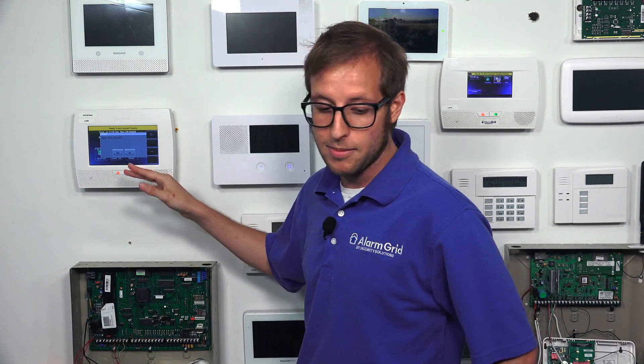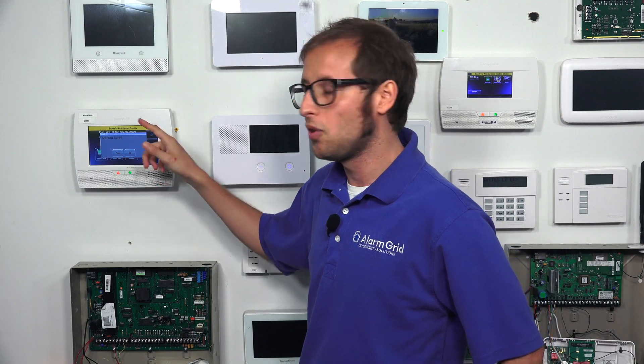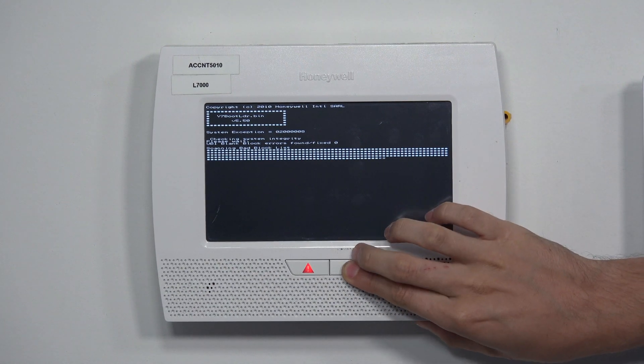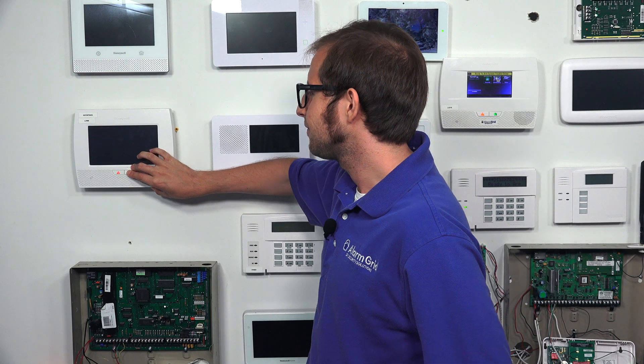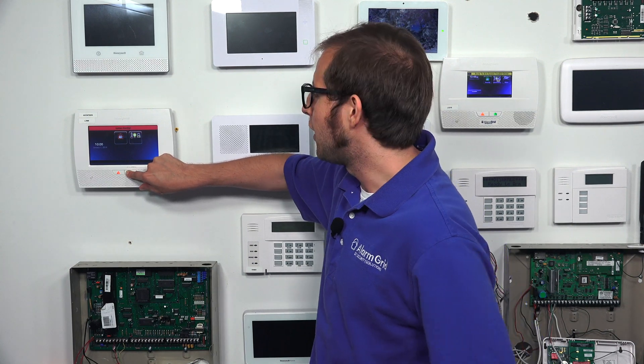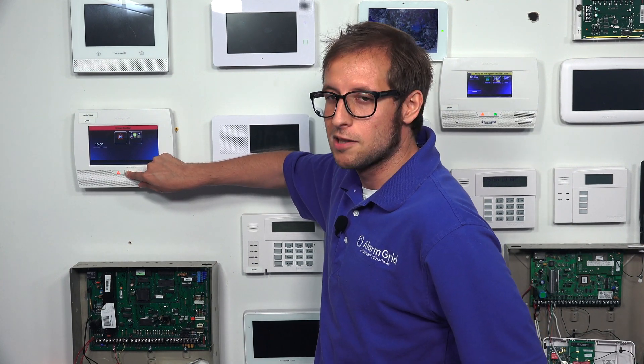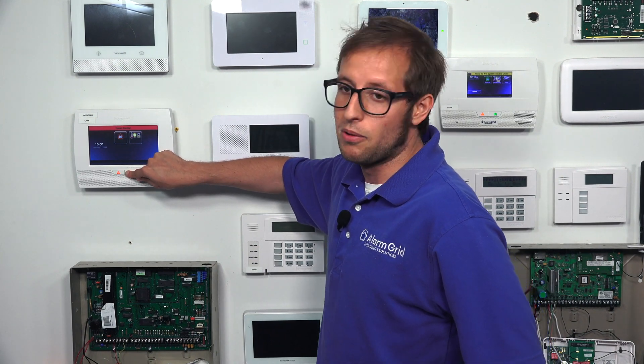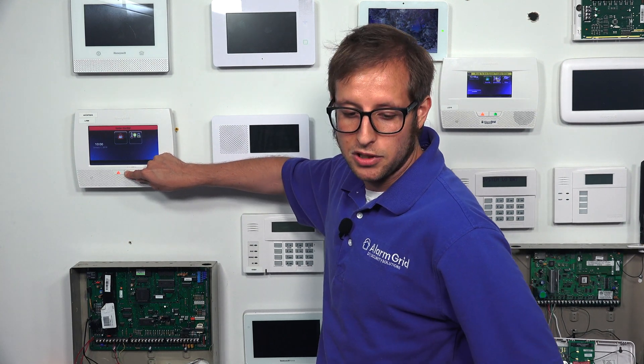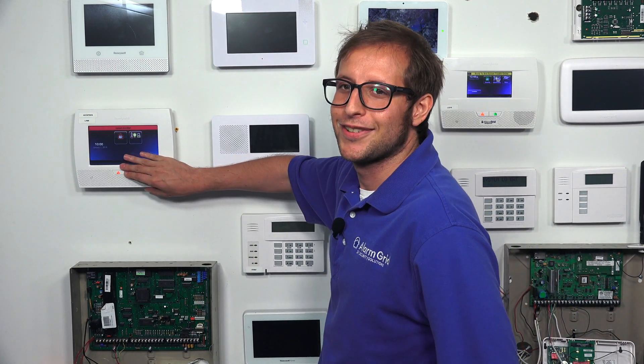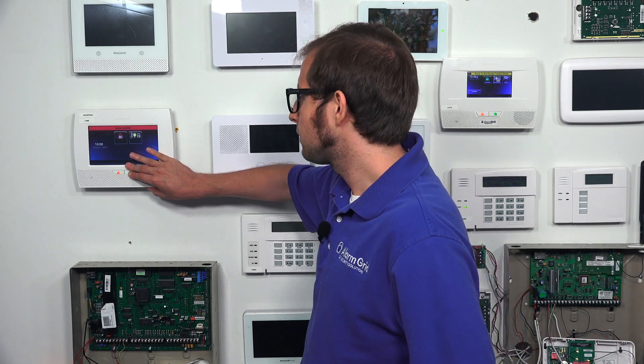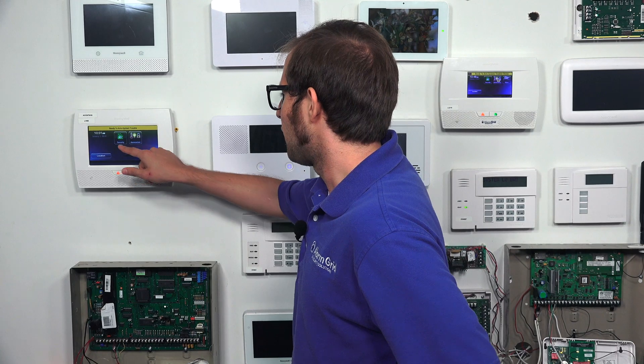Once the system is lighting back up, we're going to press and hold the Home button until the bar at the top changes. I'll demonstrate that now — we press Yes, wait for the reboot process to begin, and press and hold the Home button. We have to hold this for a while, so this will be sped up. We keep holding down this button until the top bar changes — in our case it will probably show a trouble condition because our battery is low, but if you get the Ready to Arm indication, whether the top bar is green or yellow, that's when you let go.